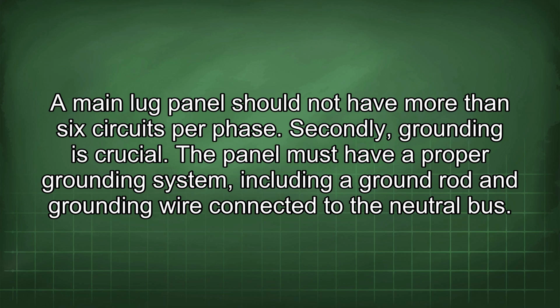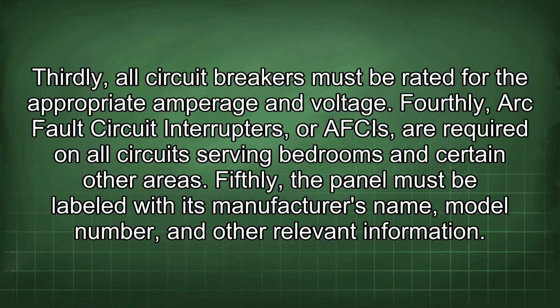Secondly, grounding is crucial. The panel must have a proper grounding system, including a ground rod and grounding wire connected to the neutral bus. Thirdly, all circuit breakers must be rated for the appropriate amperage and voltage. Fourthly, arc fault circuit interrupters, or AFCIs, are required on all circuits serving bedrooms and certain other areas. Fifthly, the panel must be labeled with its manufacturer's name, model number, and other relevant information.